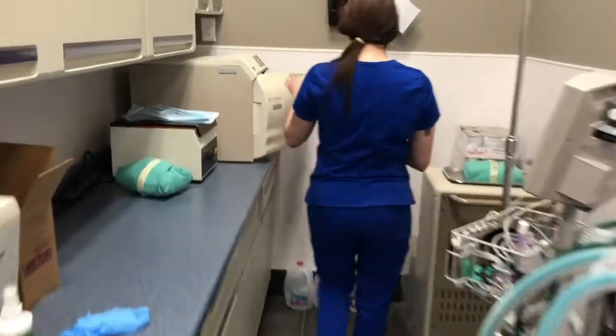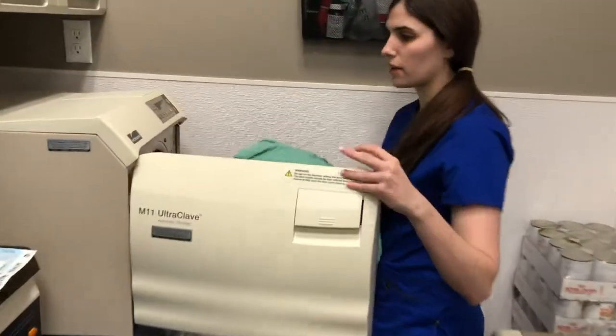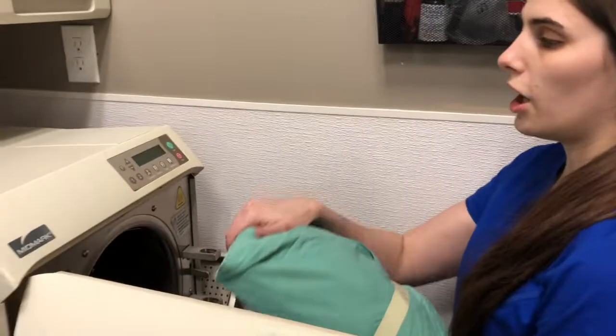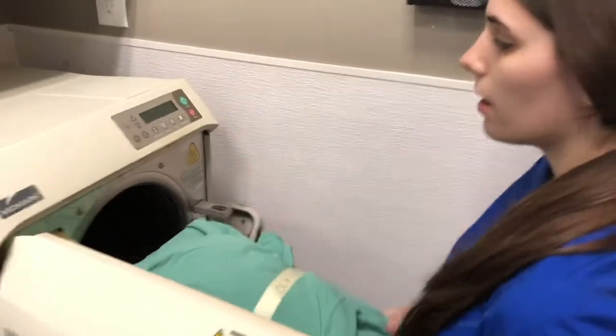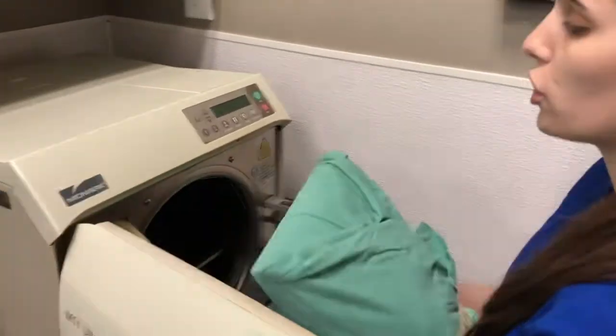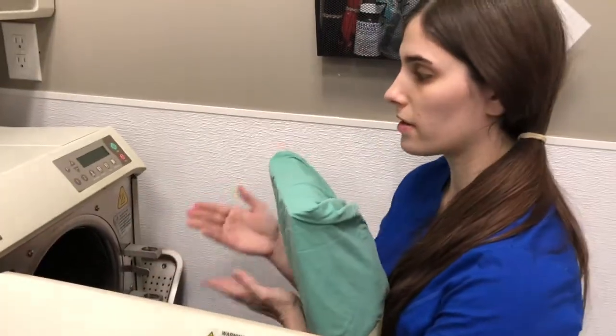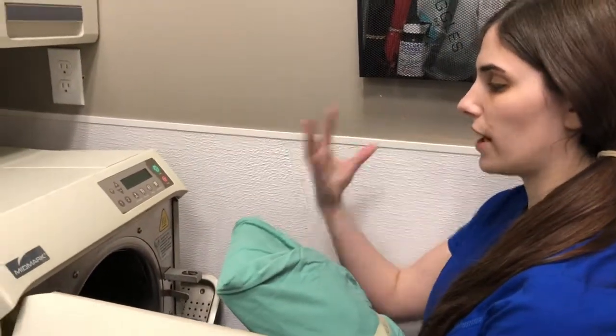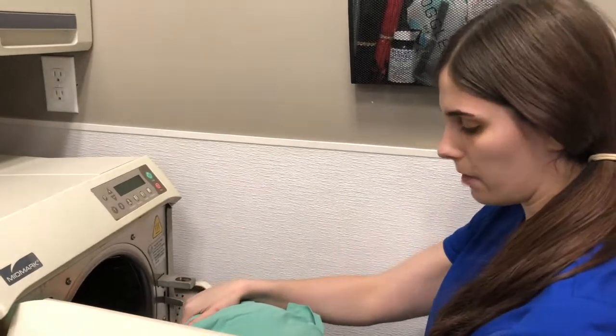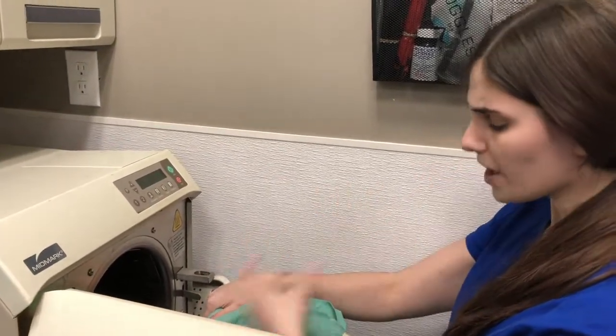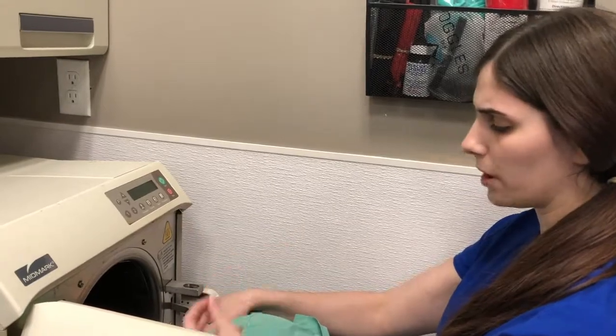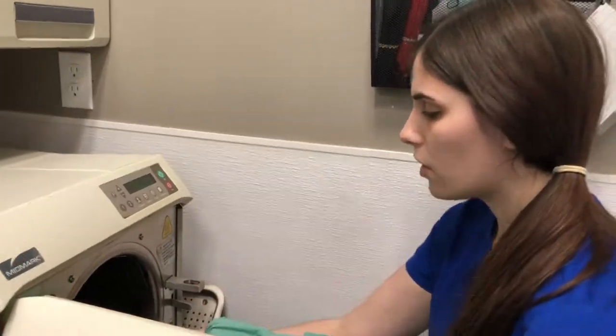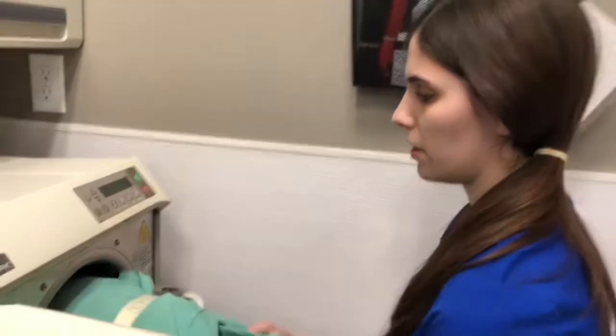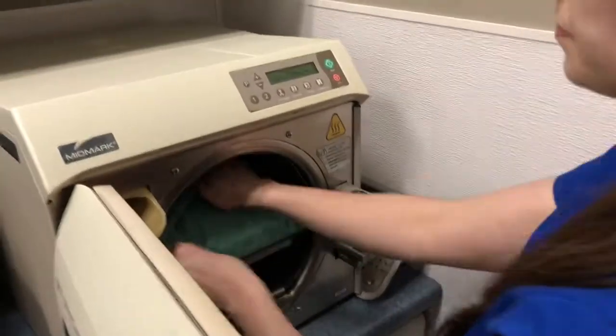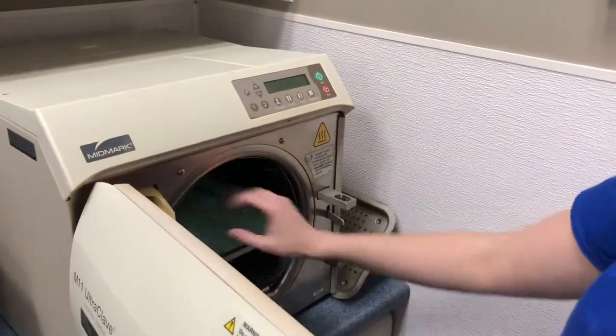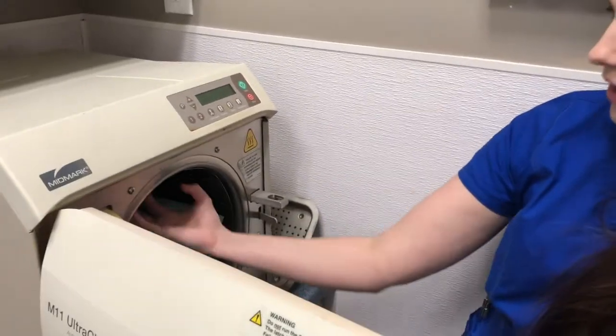So our last layer of sterilization, our last layer of cleaning is the autoclave. This is really where the sterilization happens. To pack this, you want to make sure you don't overpack it, because then the instruments will, I guess, feign sterility, but they won't actually be sterile because the bacteria won't be able to vent out, or the heat won't be able to vent out the steam. So they have these grates here, and what I'm going to do is just place this OVH pack in here by itself for now. That way the steam can come up and then come out.